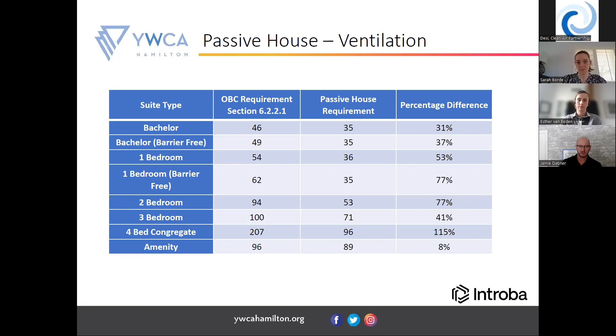We analyzed probably 5 or 6 different ways to do ventilation for the building. We looked at doing it in every single suite, we looked at doing maybe every 2 floors with distributed machines, we looked at doing risers with machines on top of each riser, and we ended up on this strategy: centralized by occupancy. One ERV on the roof handles all the residential suites, and another is set up to run the program areas on the basement and ground floor. The idea was keeping the penetration number low, so we're not going in and out of each suite twice - less bridging, less sealing in the envelope, less thermal bridging, and keeping the floor-to-floors low.